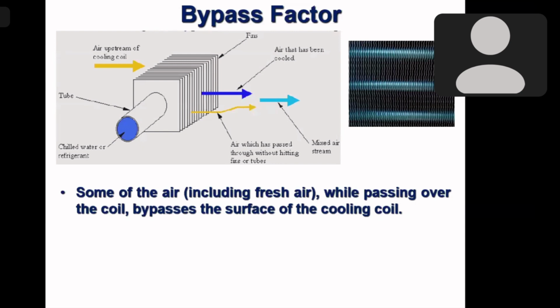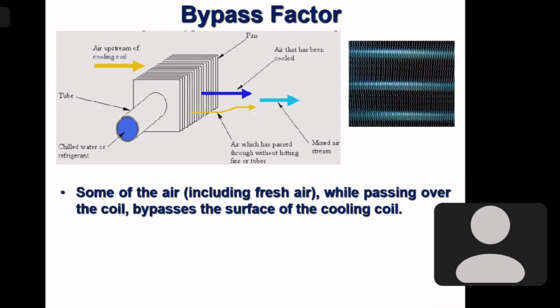We cannot increase it more, because if we increase the number of fins, then it will provide enormous resistance to the airflow. So my air handling unit fan has to be very high pressure. Very high pressure means very high power and very high power consumption. So there is a limit. So it's around 10 to 13, 14 fins per inch length.